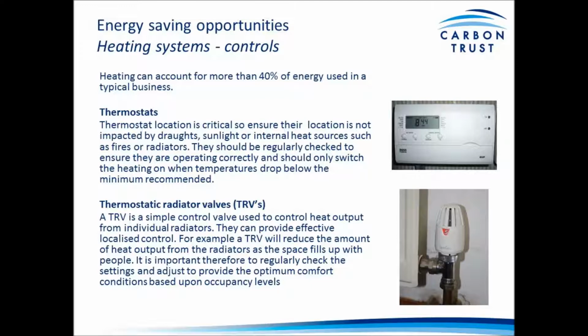Thermostatic radiator valves don't control the boiler. They reduce the flow of water through the radiator, which they're fitted to, when the temperature goes above a certain setting. So you want to set them to the level you want in the room. Lower settings use less energy, so it'll save you money. Be careful when using radiator covers. TRVs sense air temperature around them and control the flow rate depending on what level they're set at. So having a cover over the radiator means that the TRV is enclosed, which is likely to make it feel the room temperature is warmer than it actually is. But these are effective ways of controlling a basic heating system locally and centrally.